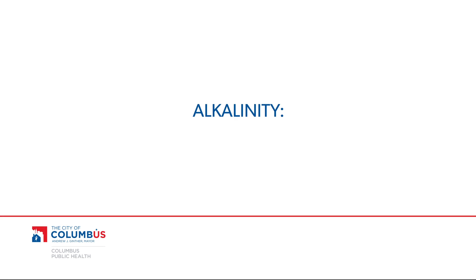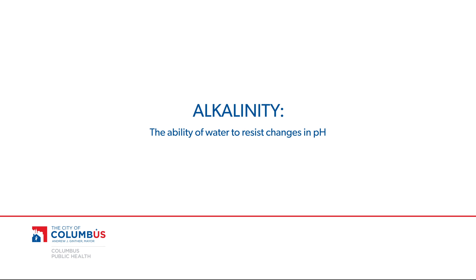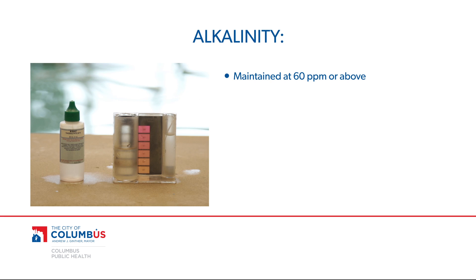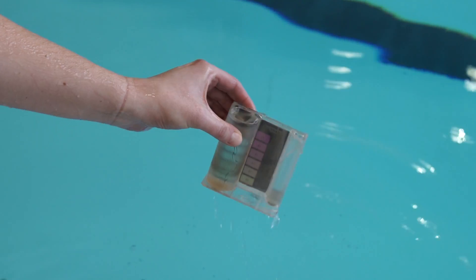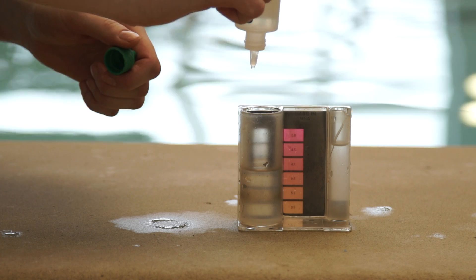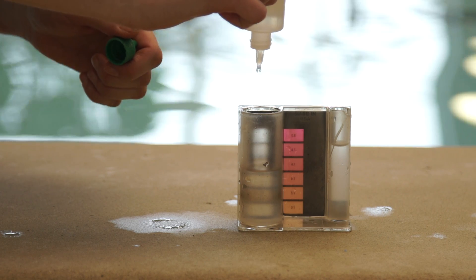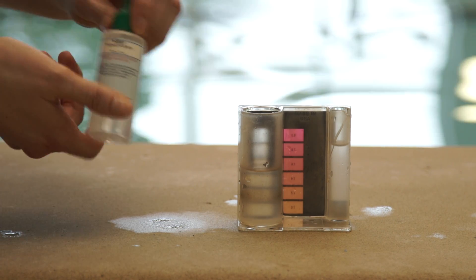Another aspect of balanced water is alkalinity, or the ability of water to resist changes in pH. Alkalinity should be maintained at 60 ppm or above and tested at least once per day. To test the alkalinity level, rinse and fill the comparator tube and then add the reagents per the test kit's instructions.